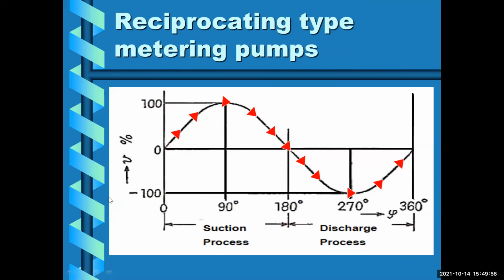In comparison to the gear pumps, reciprocating type metering pumps are less susceptible to the physical parameters of the liquid. However, without improvements in the basic design, reciprocating type metering pumps generate large pulsation in the suction and the discharge process. The sine wave shown reflects the flow velocity during the suction and discharge cycles. To minimize pulsation and improve discharge accuracy, metering pump manufacturers have come up with various designs. I'd like to show you two very good designs.